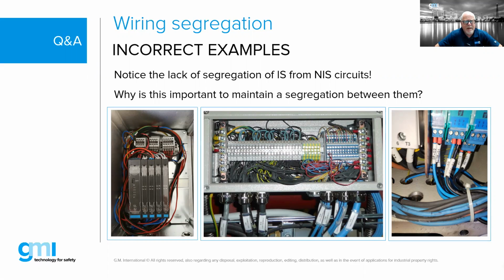In this situation, someone has run cables all around those IS barriers, defeating the 50 mm separation between IS and non-IS. The same issue appears in the panel on the top right—it looks fine from outside, with IS cables on the right and non-IS cables on the left, but once opened up, there are loops and bunches mixed together.